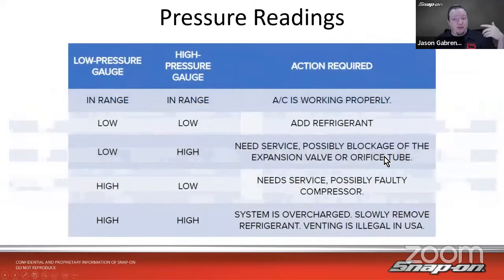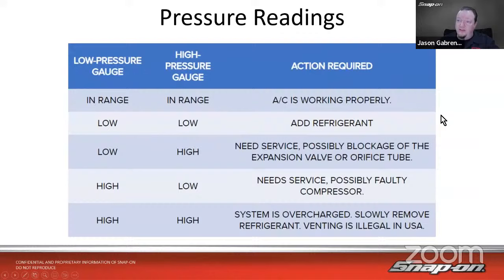And then, of course, with that chart, what does it mean? So if they're both in range, you're good. If they're both low, it probably needs refrigerant. Maybe it has a leak. We don't really go into leak detection in this particular class, but maybe there is a leak somehow and you might need to add refrigerant. If the low side's low and the high side's high, then possibly blockage of the expansion valve or orifice tube, depending on what it uses.